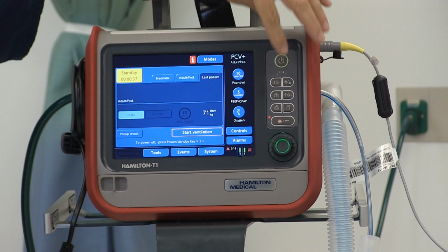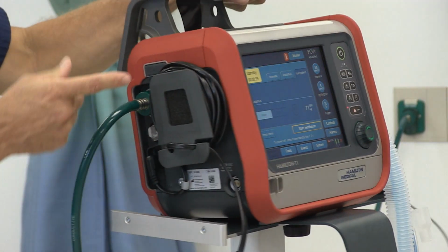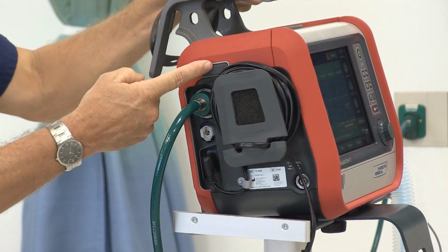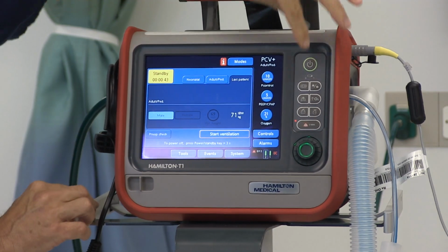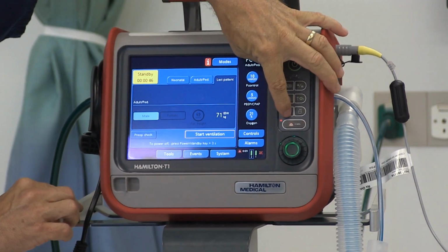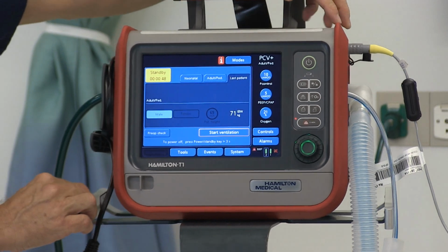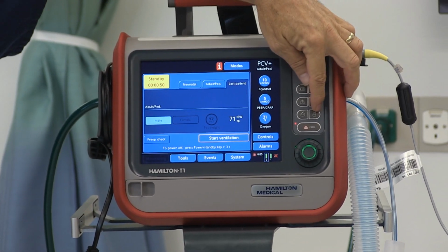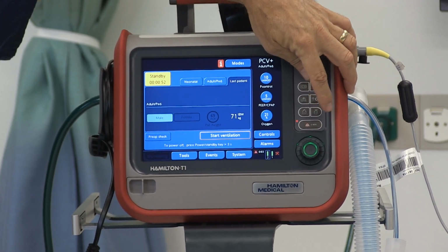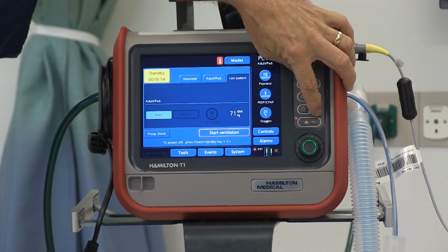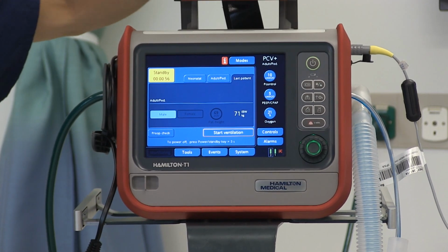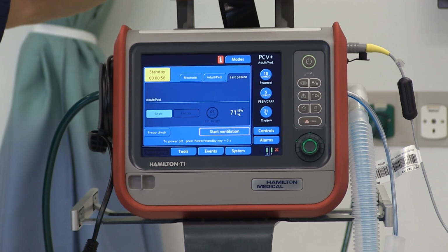That is the screenshot button. So once I've put a thumb drive in the USB port, this becomes like a shutter button. Every time I push that button, it takes a picture of the screen. To the right of that is the nebulizer button. The ventilator does have an internal nebulizer. I can depress that button. It's going to run the nebulizer for 30 minutes and turn itself off.